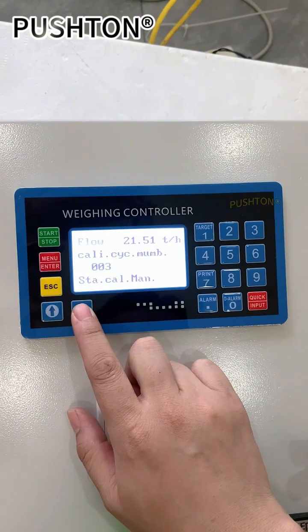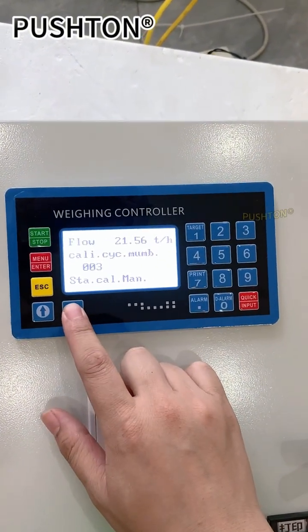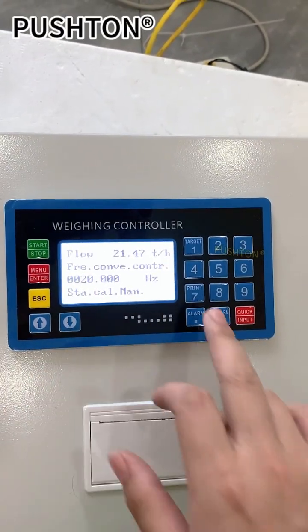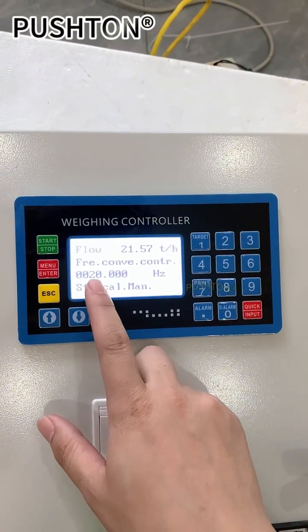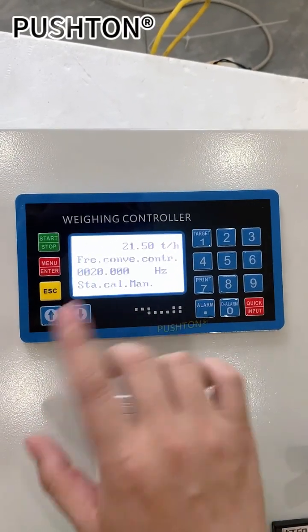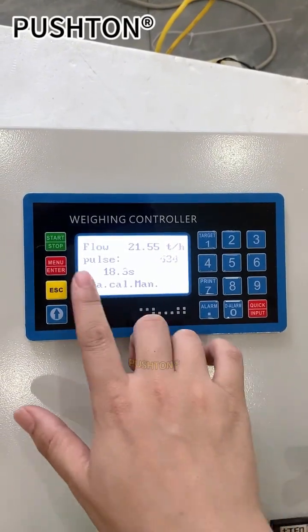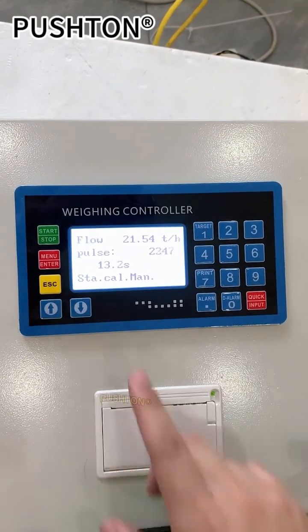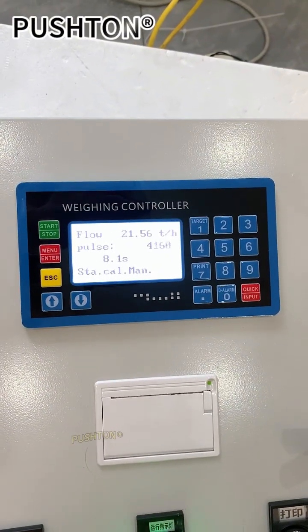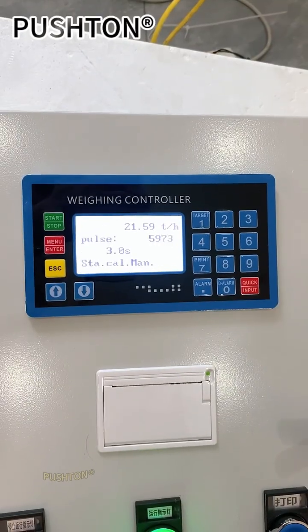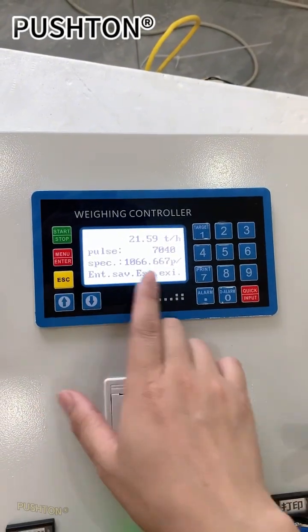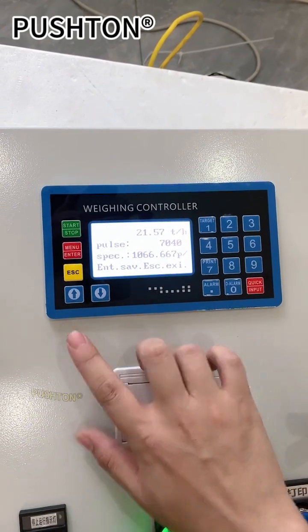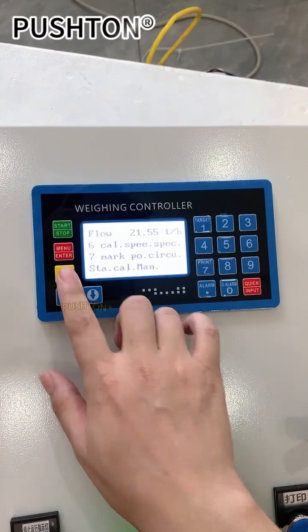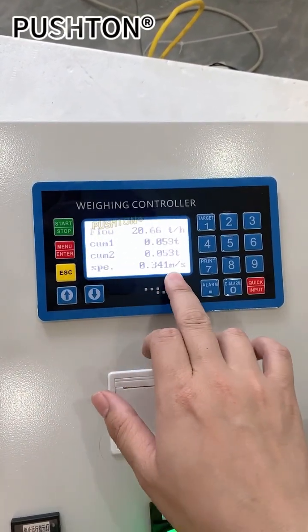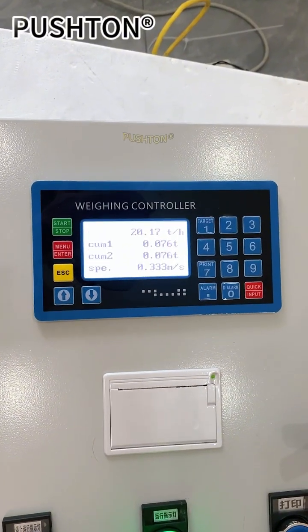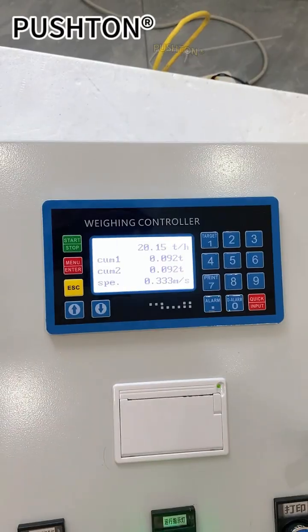Down arrow. Calibration cycles. The default is 3 cycles, so don't touch it. 50 Hz means, if there is a frequency converter, just turn it to 50 Hz. If there is no frequency converter, don't touch it. Down arrow. Timing calibration speed specification. This is the pulse value being calibrated. When this time becomes 0, the calibration is completed. When the time becomes 0, our speed specification has been generated. Then press enter to save it. Press the return key to return to the main interface. Now the speed has been measured: 0.33 meters per second. Done.